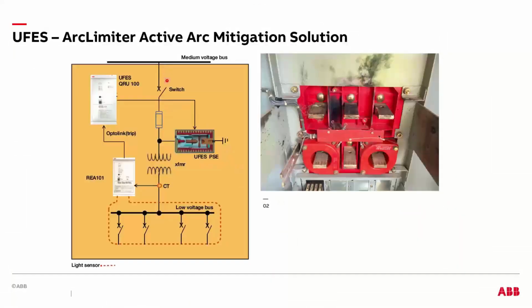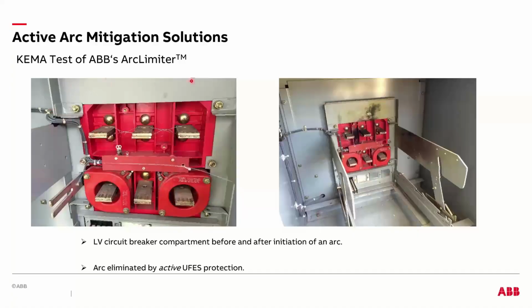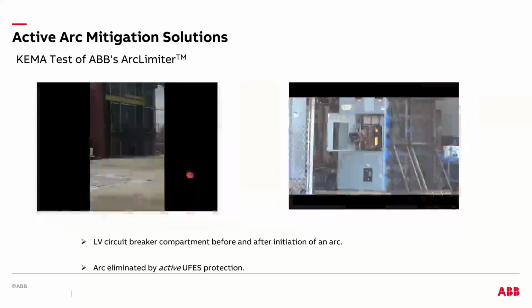So for this particular setup, where you have a fused switch connected to a distribution class transformer with low voltage equipment on the downstream side, we have actually performed a KEMA testing, and these are some of the pictures, and let me show you guys. So this is the KEMA setup for the low voltage equipment, where you can see the wire that is run across the phases in order to simulate an arcing fault, and then you have a point sensor that is looking for the light, right? So this is a part of the arc flash relay.